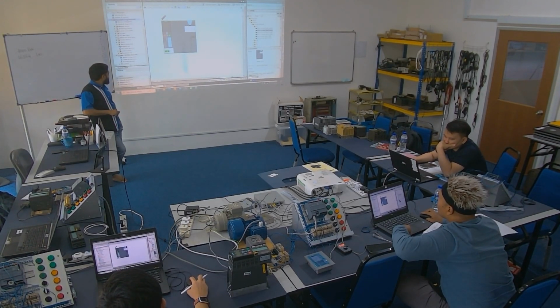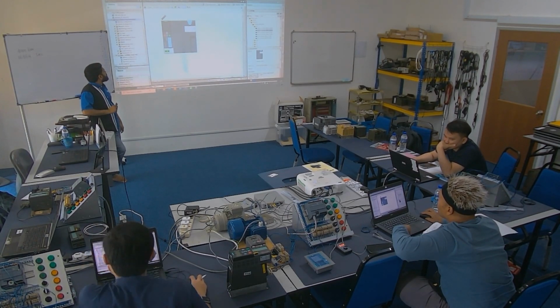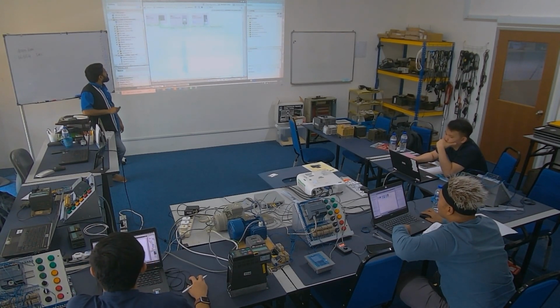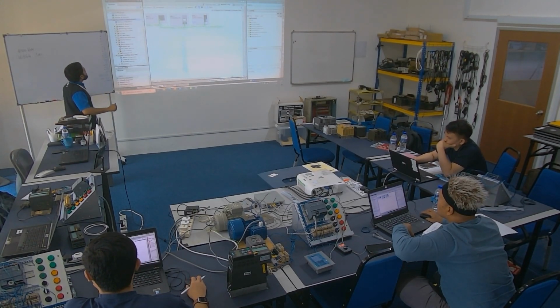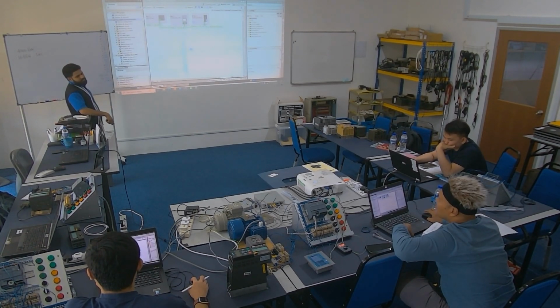Because this is the drive, when you go back here, inside your PLC you have this configuration. First I download the PLC configuration — meaning we're not programming, just downloading the config, not the program. So right click the PLC, download to device, hardware configuration, and start the download.